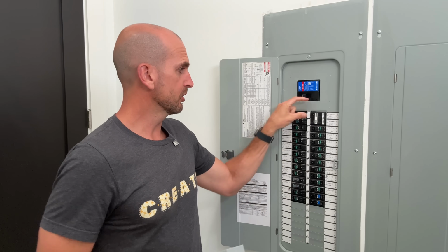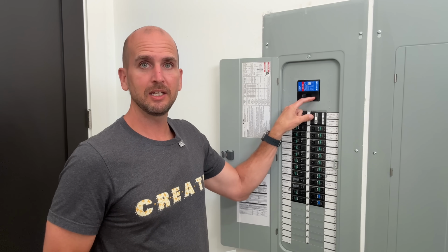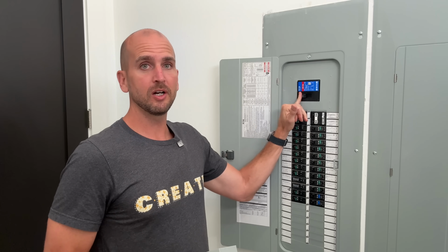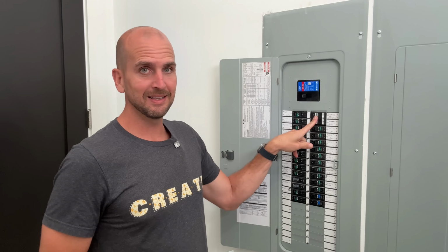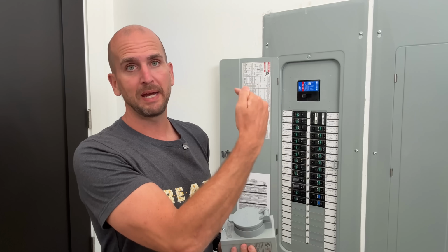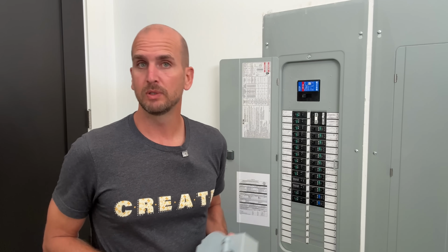Just don't forget, you're gonna need an interlock kit here to make sure your main's on or your generator inlet is on, and never both of them on at the same time, or you would backfeed the grid, which is something you do not want to do.